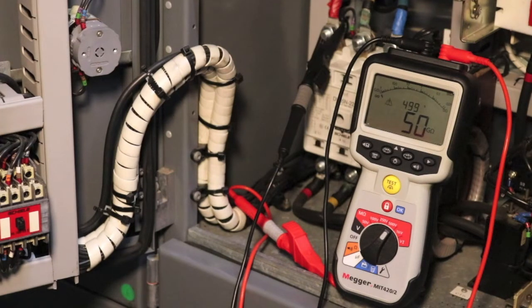Let's see we've done 100 seconds and we're up to 50 gig ohms now. Hopefully the insulation should just keep going up and up until it reaches its final value. It's not much of a spectator sport so I'll turn the camera off now and then we'll reconvene towards the end of the test.